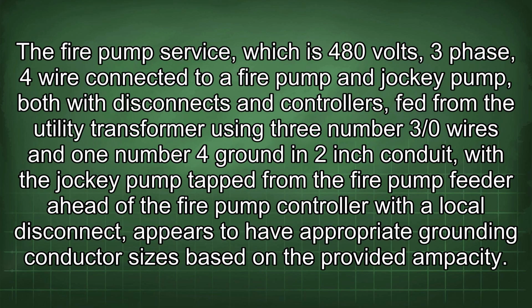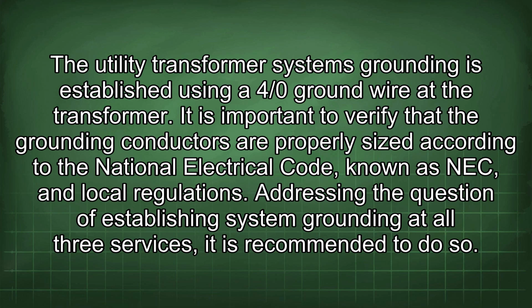The fire pump service, which is 480 volts, 3-phase, 4-wire connected to a fire pump and jockey pump, both with disconnects and controllers, fed from the utility transformer using 3 number 3/0 wires and 1 number 4 ground in 2-inch conduit, with the jockey pump tapped from the fire pump feeder ahead of the fire pump controller with a local disconnect, appears to have appropriate grounding conductor sizes based on the provided ampacity. The utility transformer system's grounding is established using a 4/0 ground wire at the transformer.